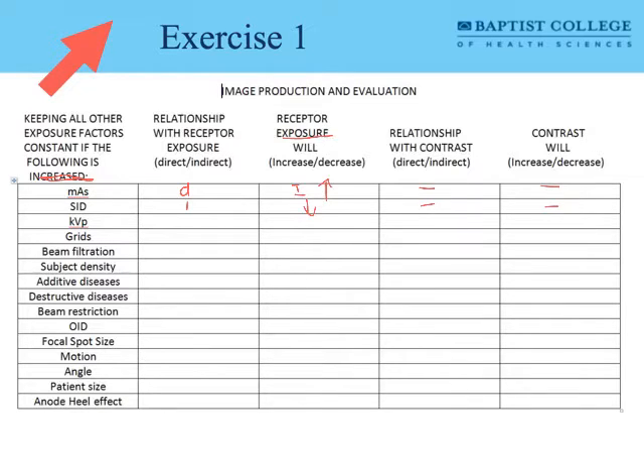KVP is a major technical factor. It has a direct relationship with receptor exposure, so as KVP increases, we would expect receptor exposure to increase. Interestingly, it also has a relationship to contrast — as KVP increases, image contrast decreases. So we call that an indirect relationship with contrast: as KVP increases, contrast decreases.